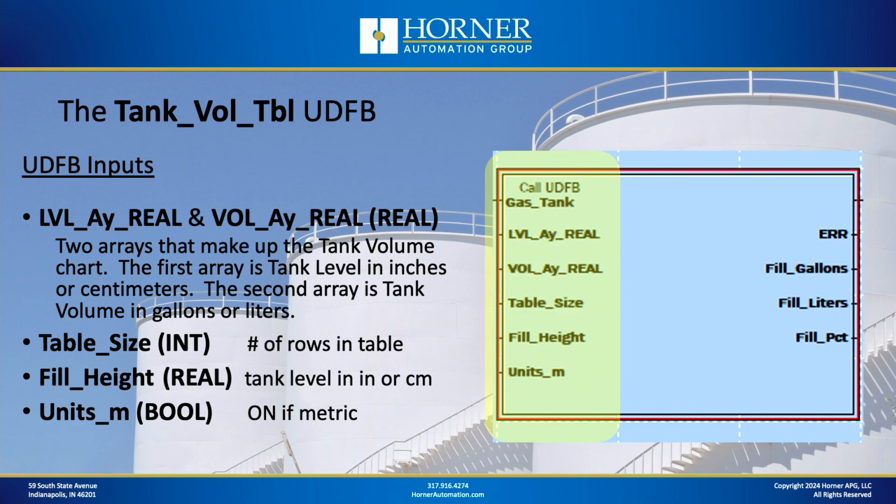Remember, a user-defined function block is, at its heart, just a function block that has inputs and outputs. All right, let's take a look at the inputs, which are highlighted there on the left. A big question you may have is, how would you get data table information into your logic? Well, you're going to do it in the form of two arrays: one array for the column of level data, in inches or centimeters, and another array for the column of volume data, either gallons or liters.